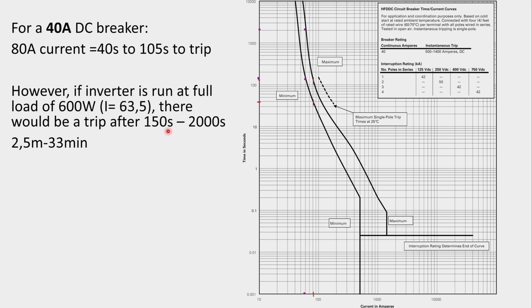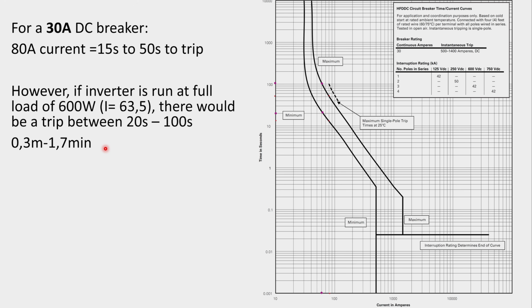How did I work that out? Because I looked at the full load current, which is 63 amps, which is sitting here, because that's 20, 30, 40, 50, 60. And the purple dot is there, so that's 150, there, 150. And the maximum characteristic line is there, which is 2000 seconds. And if you go even lower, look at a 30 amp circuit breaker. So if somebody puts a load on the inverter that requires 80 amps, it'll trip from 15 seconds to 50 seconds. So within 50 seconds, the circuit breaker would have tripped.